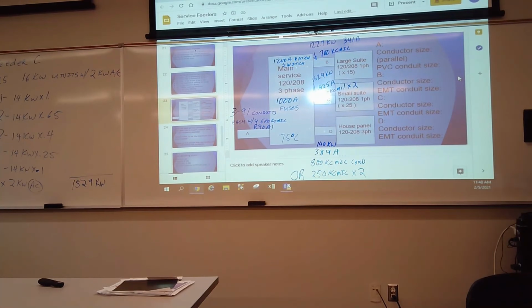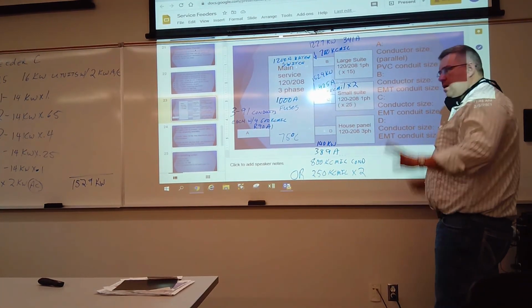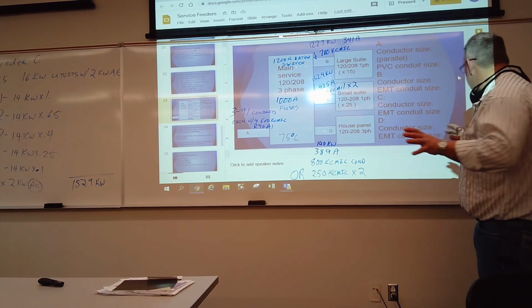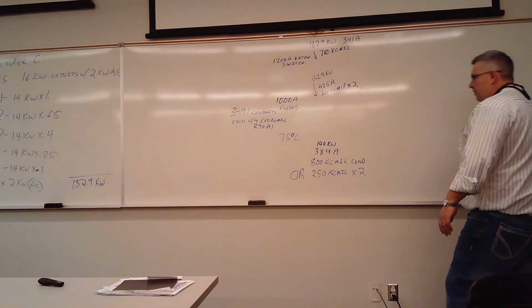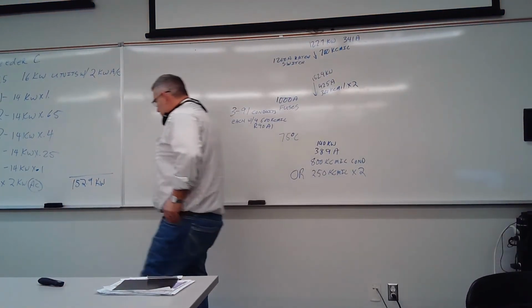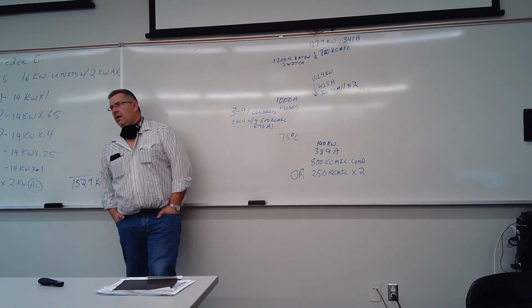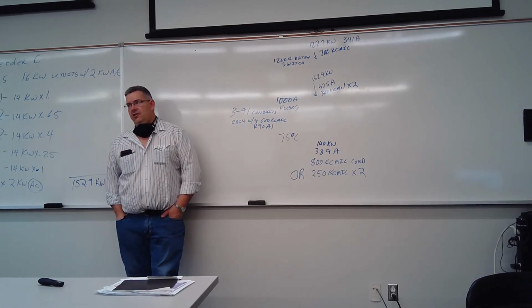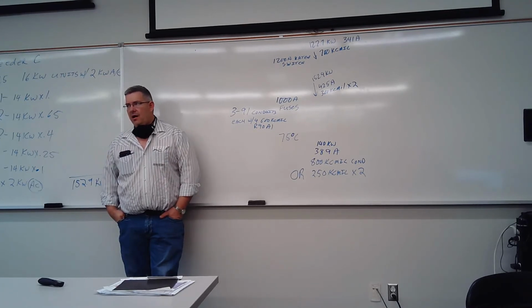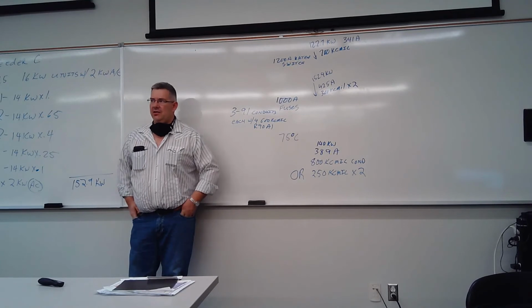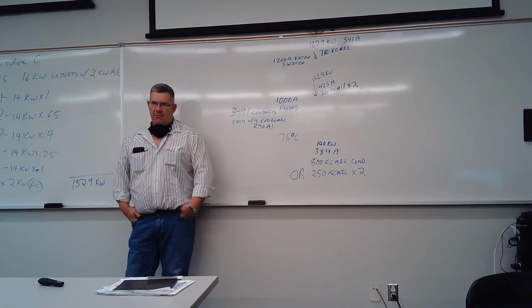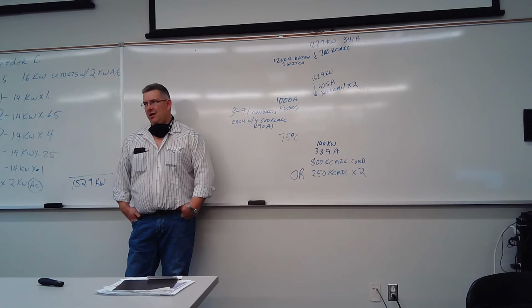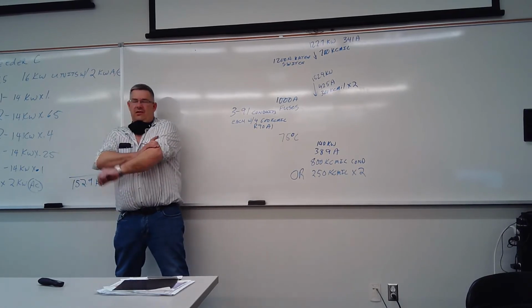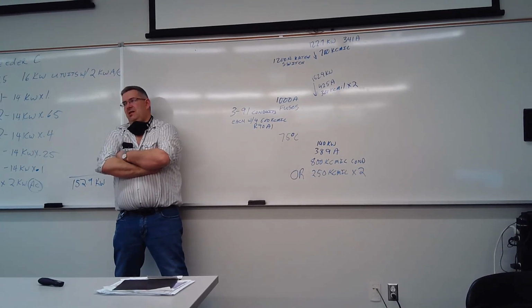For the purposes of this class, choosing between parallels, everybody's done with this, right? Yeah, I'm going to shut that glaring thing off. For the purposes here, is there a right and wrong between picking parallels or not? Or aluminum versus copper? I usually specify whether I want aluminum or copper conductors. When you get anything bigger than number 3 copper, anything over 100 amps, quite often aluminum is the way to go because it becomes so much cheaper. That's just kind of a rule of thumb.